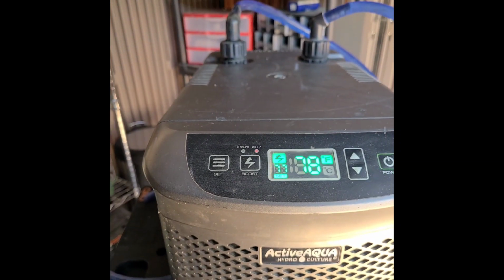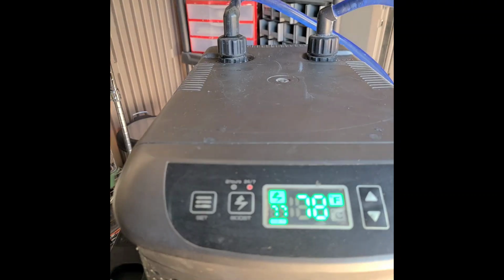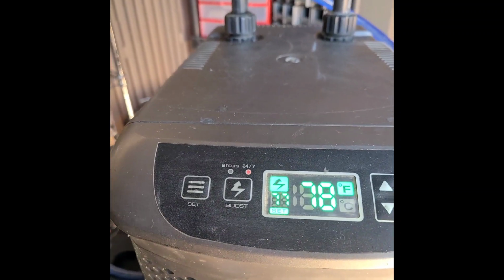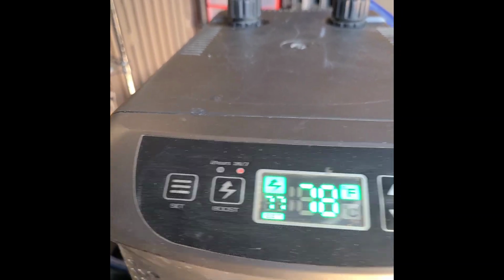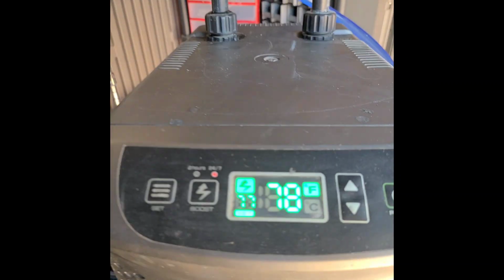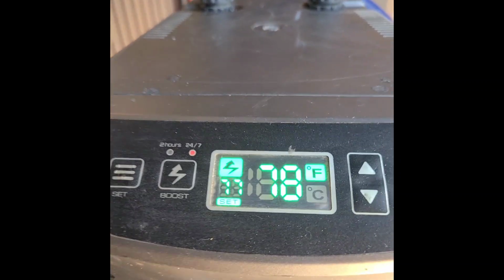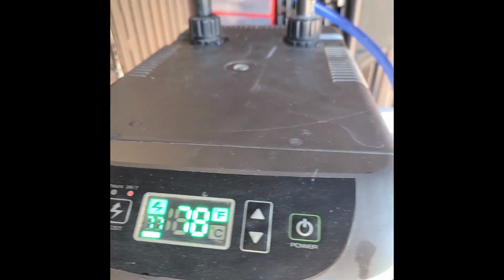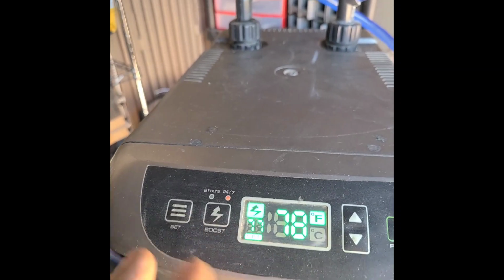Now when we initially started this system today - once again this is a 2.5 gallon reservoir - I believe the water was 86 degrees and it was 93 in the room, and that was maybe 15 minutes ago. I had set the chiller for 77 degrees Fahrenheit. Now it bumps back up to 78 because it has a plus or minus 3 degree range, so this is still in the comfort range.